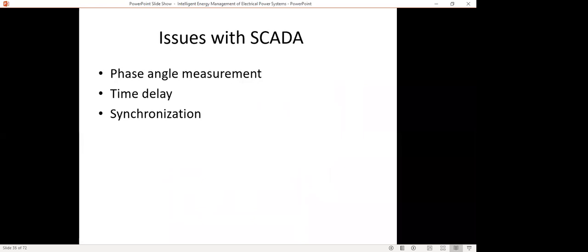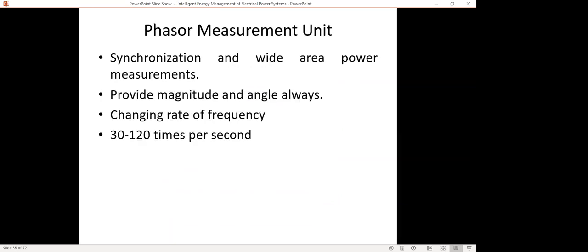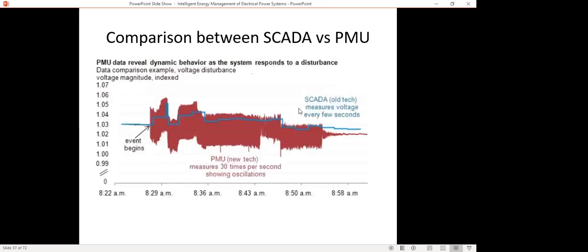Earlier we used the SCADA more, but we have different problems with SCADA because it does not collect information continuously. It collects the information at different intervals, and the intervals are large. So phase angle measurement problems, time delay, and synchronization issues led to bringing the phasor measurement unit into the systems. The phasor measurement units have more synchronization. They can provide magnitude and the changing rate of frequency. We can collect the data 30 to 120 times per second. In 1 second, we can collect from 30 to 120 samples. So here we have a comparison figure between the SCADA and the PMU.